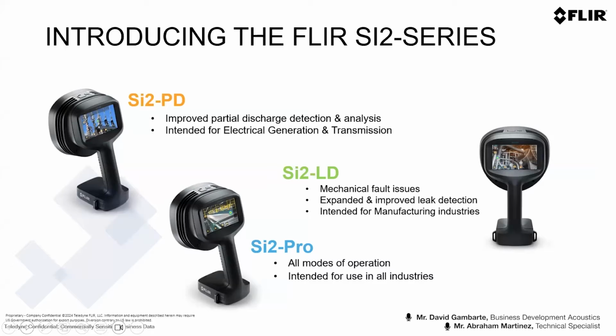Our acoustic cameras are used in the market to find partial discharges and to get the analytics on those partial discharges. Our analytics are powerful, and now in the Si2 PD they are included on camera. So when you're on field or doing an inspection, you will get the analytics of every one of the partial discharges that you're finding on camera. So you can naturally save every one of the snapshots of the data you are taking, but also take quick actions on those that require a quick action.